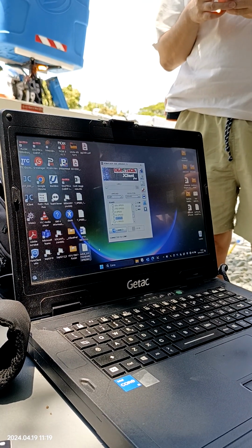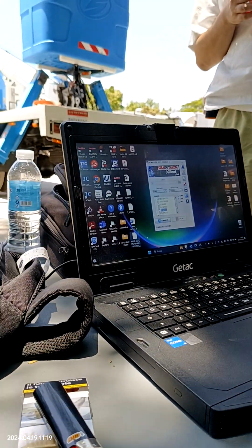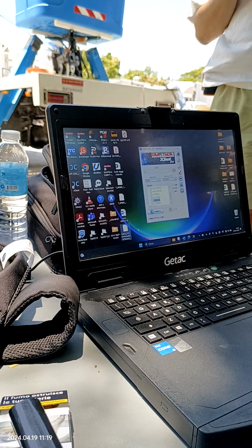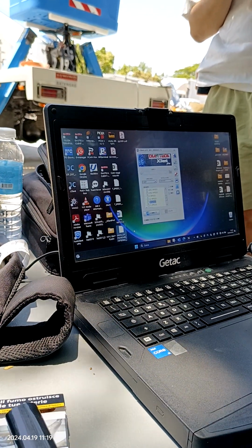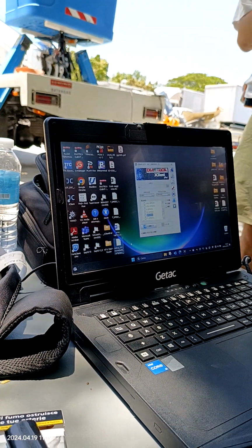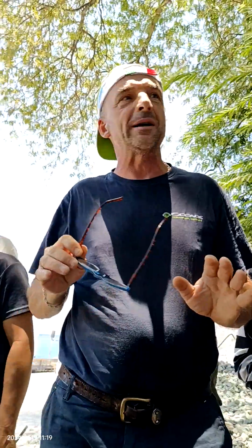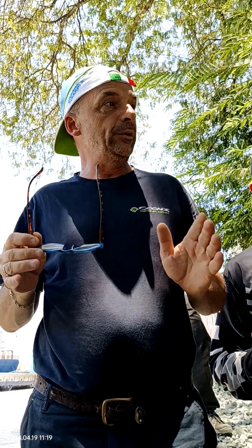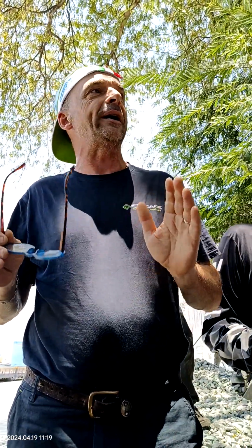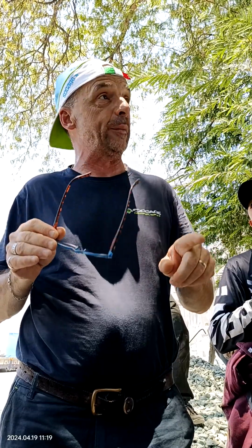Guys, this is very important because anything can happen. For example, you burn a board, you replace the board, you cannot open the board because it's broken, I don't know. You replace it with a new one. Remember that when you order some parts from Italy, you know better than me, inside any board there are firmware and software. The firmware normally is the board. Normally it is shipped already with the correct firmware inside.